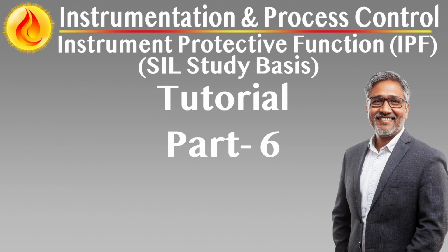Operational considerations for maintenance overrides. Maintaining situational awareness and control during temporary IPF disablement. From an operational perspective, maintenance overrides introduce a temporary but significant shift in the plant's risk profile. While necessary for inspection, calibration, or troubleshooting, overrides reduce the facility's protective layers, placing greater responsibility on operations personnel to monitor the process and manage any deviations manually.